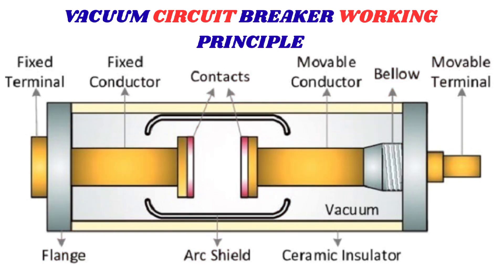Having known the properties of the vacuum environment, how do vacuum circuit breakers work? The functioning of vacuum circuit breakers is based on the principle that arcs can be rapidly extinguished when they occur in a vacuum, allowing for efficient interruption of electrical currents. When a fault occurs in any section of the power system, the vacuum circuit breaker operates and the contacts separate — an arc is established. The vacuum environment rapidly extinguishes the arc, making ionization almost impossible, thereby interrupting the circuit and eliminating the arc formed.